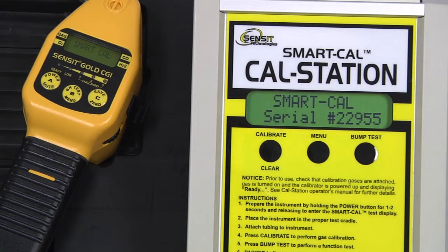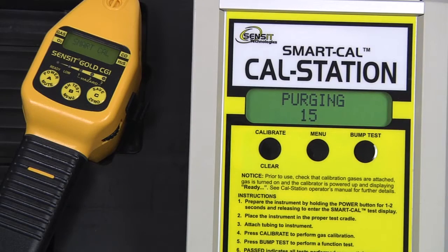The instrument has been found, there will be a flow check, and a 60 second purge. After the purge is complete, the instrument will auto-zero, and then calibration will begin with either 50% LEL methane or propane.